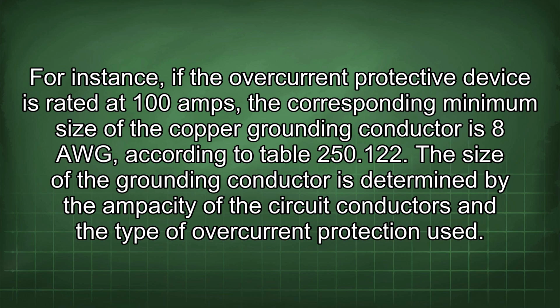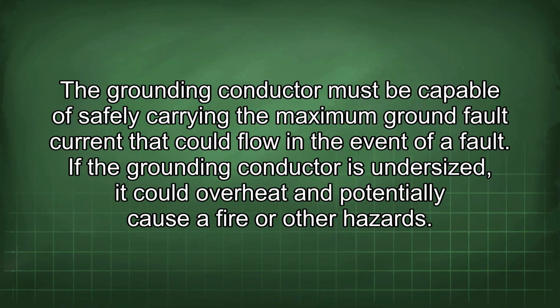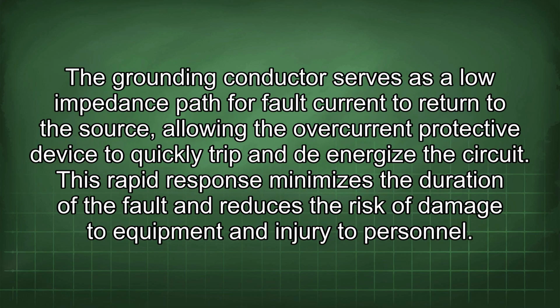250.122. The size of the grounding conductor is determined by the ampacity of the circuit conductors and the type of overcurrent protection used. The grounding conductor must be capable of safely carrying the maximum ground fault current that could flow in the event of a fault. If the grounding conductor is undersized, it could overheat and potentially cause a fire or other hazards. The grounding conductor serves as a low impedance path for fault current to return to the source, allowing the overcurrent protective device to quickly trip and de-energize the circuit.